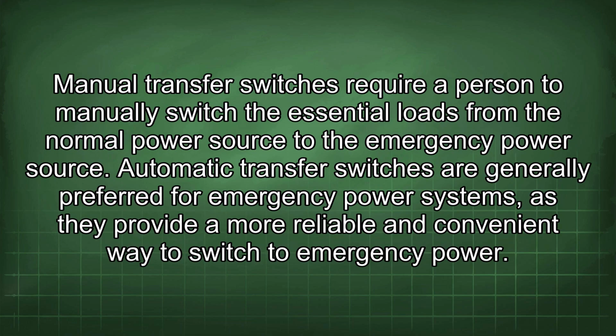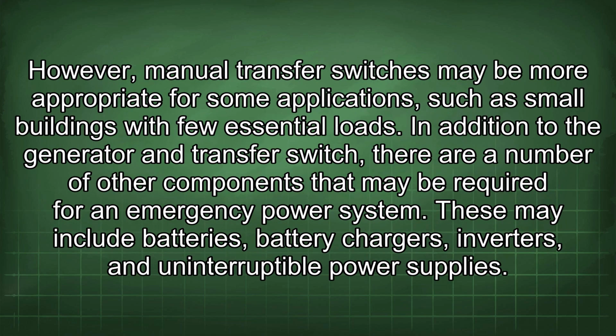Manual transfer switches require a person to manually switch the essential loads from the normal power source to the emergency power source. Automatic transfer switches are generally preferred for emergency power systems as they provide a more reliable and convenient way to switch to emergency power. However, manual transfer switches may be more appropriate for some applications, such as small buildings with few essential loads.